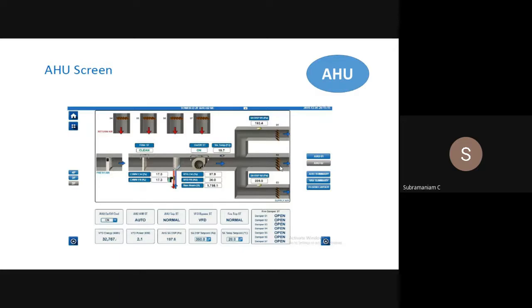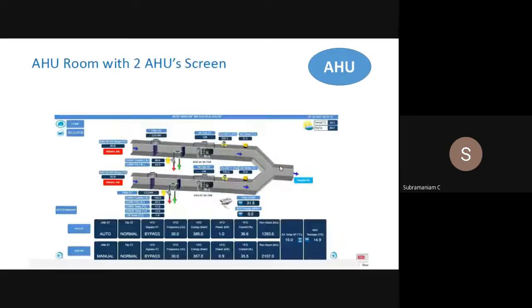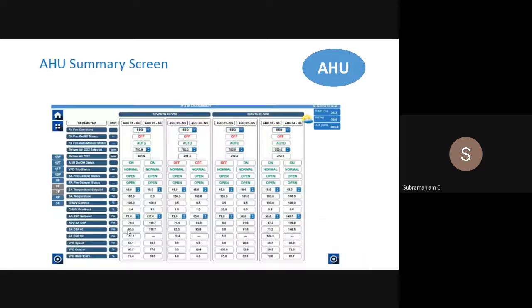Once we have all the IO points wired, the systems programmed, and graphics done as per our requirement for every job, we can do that part. So these are some sample graphics. This is like 2 air handling units supplying one built space, some 30,000-40,000 square feet. We can get the tonnage, because 1 BTU meter is there in the line. All these values we can see there.